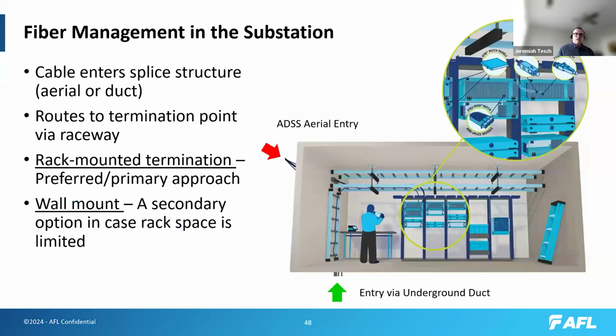And then once you get into the substation, you have your ADSS entering aerially or your underground duct entry from the bottom. So then you'll route your cable to the termination points via the raceway. You have rack-mounted termination, which is the preferred primary approach, and then wall-mounted solutions as a second option if you run out of rack space.